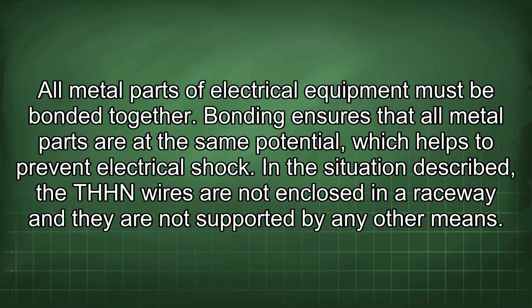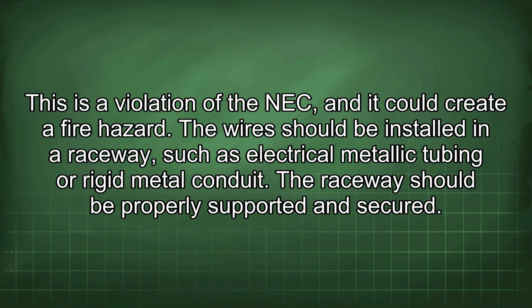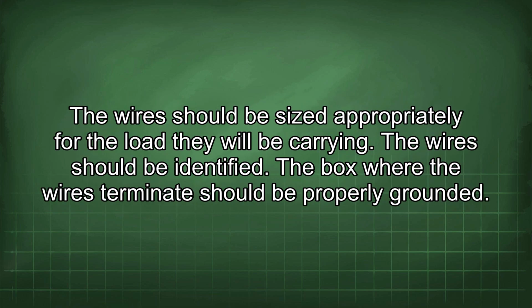In the situation described, the THHN wires are not enclosed in a raceway and they are not supported by any other means. This is a violation of the NEC and it could create a fire hazard. The wires should be installed in a raceway, such as electrical metallic tubing or rigid metal conduit. The raceway should be properly supported and secured. The wires should be sized appropriately for the load they will be carrying. The wire should be identified. The box where the wires terminate should be properly grounded.